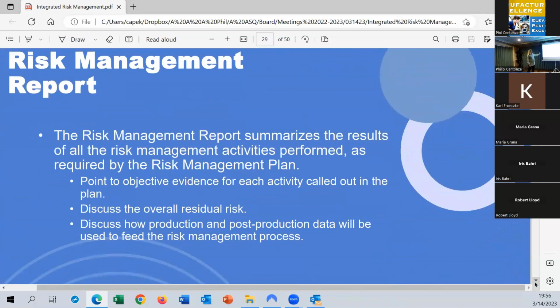For ISO 14971, the risk management report that summarizes everything that you did is an important tool and something that you use to show regulatory agencies that you do have a good risk management process, and then you follow that process in development of your product. And that's typically where you discuss your overall residual risk and your risk benefit.